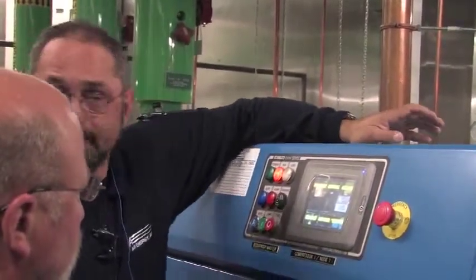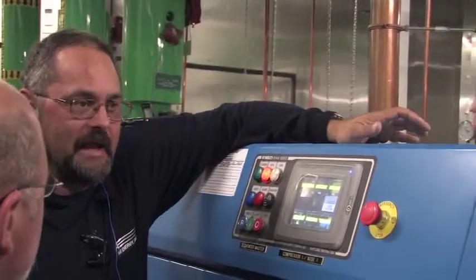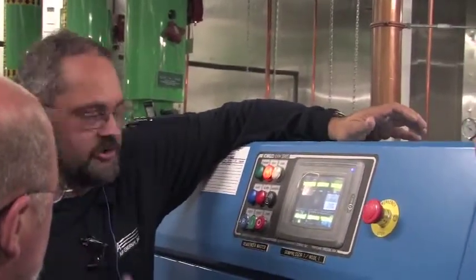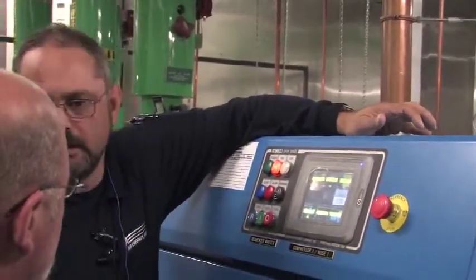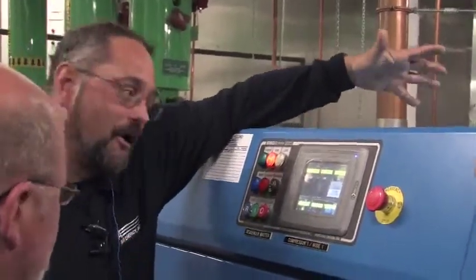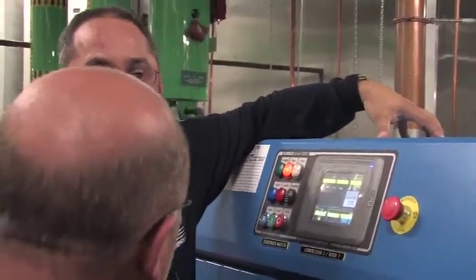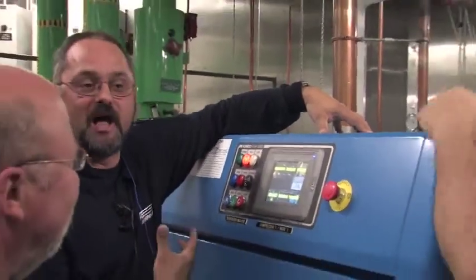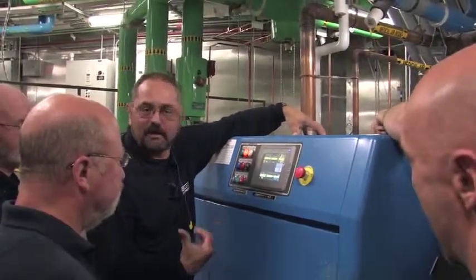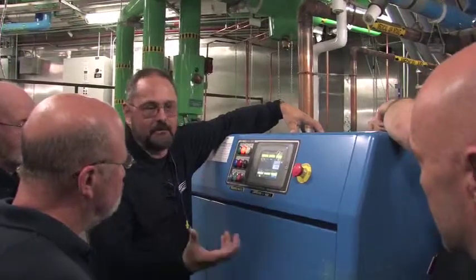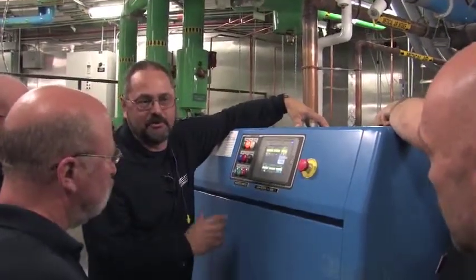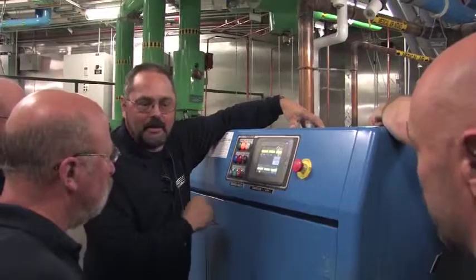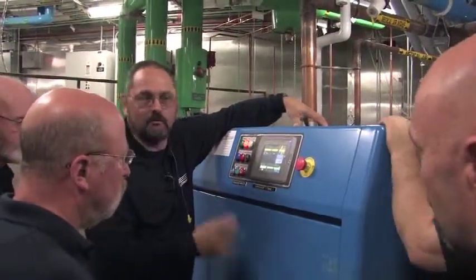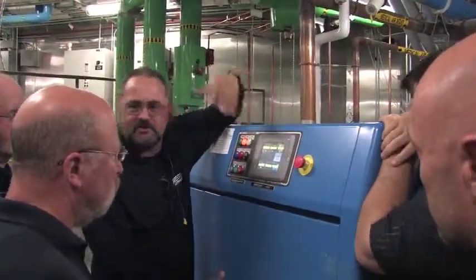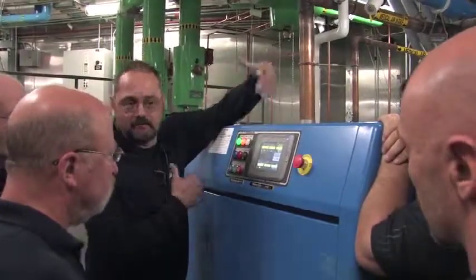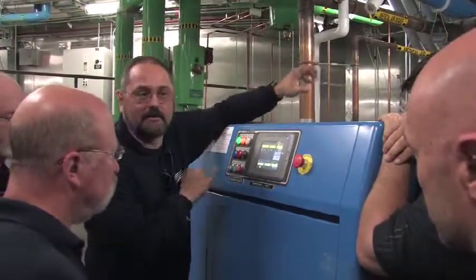And obviously, the biggest thing to remember is if you can't get it to run in the sequencer, just toggle them into local, put them in local. Call us. But the bottom line is, same thing like on our vacuum systems, we have a bypass method. The most important thing I tell people in training is this is how you get it to run quick and dirty. While you're trying to remember what he said about resetting this and doing that, meanwhile, you need something. Turn it on. It buys you time.